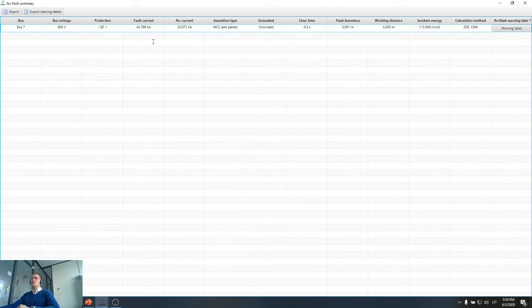So let's look quickly through these parameters here. First of all, we have information about the fault current. Fault current is quite huge. It's around 42,000 amps in case of maximum three-phase short circuit. Arc current is a little bit smaller, about 25,000 amps. Installation type is MCC and panels, as I have shown before. The network is grounded, so these parameters are needed for arc current calculation. Then we have clearing time calculated. According to the settings that we made, clearing time is around 300 milliseconds or 0.3 seconds. And the flash boundary is around 3 meters, so it means that the safe distance to stand from the bus bar in case of this huge fault current would be about 3 meters.